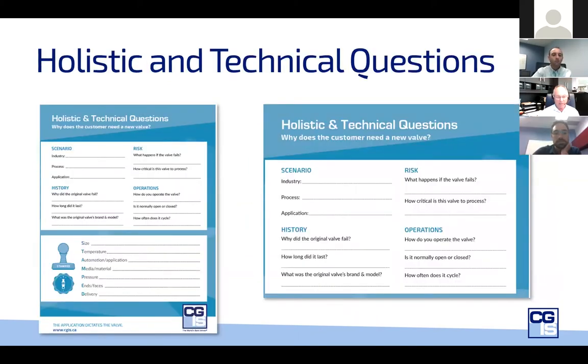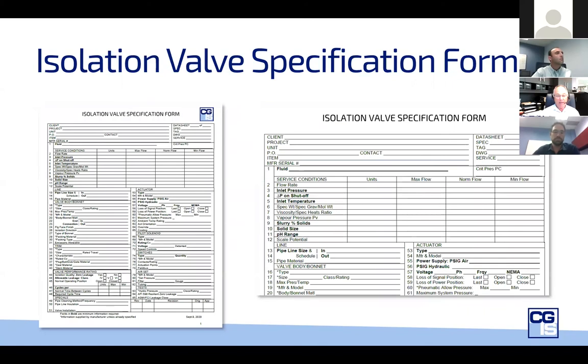We have some tools that we can provide to you. We would ask you to start questioning your own systems. The data sheet we use — we borrowed it from ISA on the control valve side. There are 85 possible item descriptions, and we bolded 20 of those. From those 20, we have enough data to really use our skill set and say, what is the best valve and technology for the application? But most importantly, items 40, 44, 45, and 46 are where we really need to know what that valve is going to do as it's isolating.